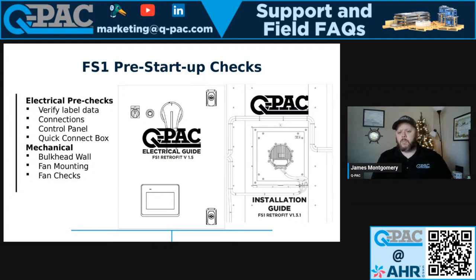The next is the quick connect box, or I call it the QCB. That's the smaller panel inside the unit. It as well has fuse protection. And it as well is going to receive the high voltage power coming out of the outlet of the control panel. So that's coming downstream of our contactor. And we'll talk a little bit more about that. High voltage, three phase, either 460, 208. And you're also going to have control voltage there.